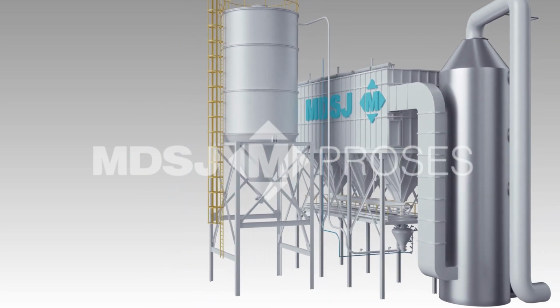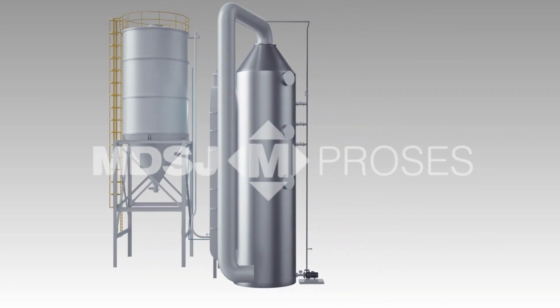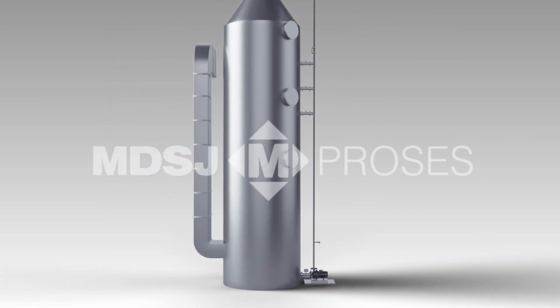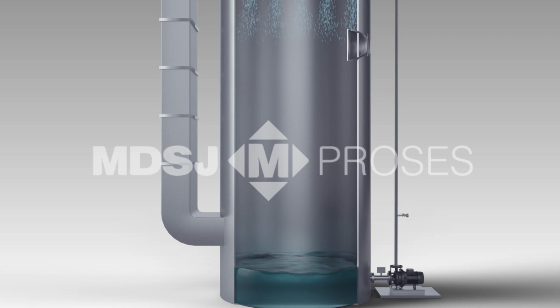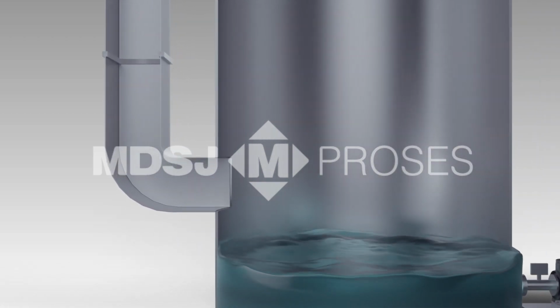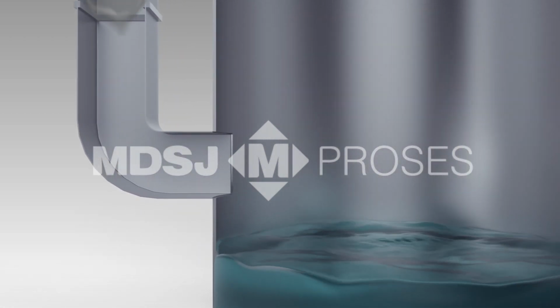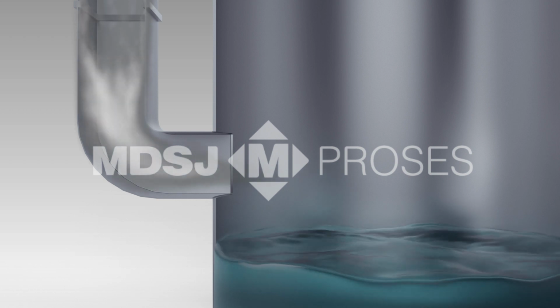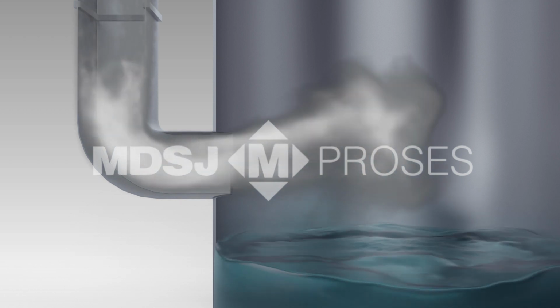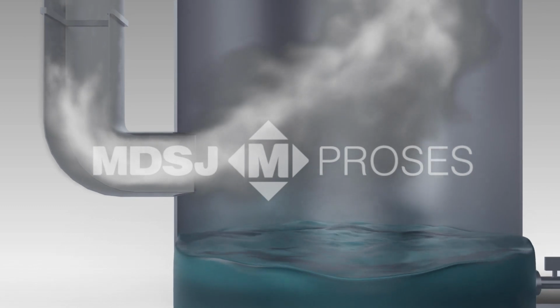Gas purified of the dust from the jet pulse filter gets transported into a wet scrubber. SO2 removal is established with the help of closed-cycle water pumps located on the scrubber by showering the gas from above with the added chemical fluids. For the removal of the NOxes in the gas, urea dosing is used at the incinerator stage.